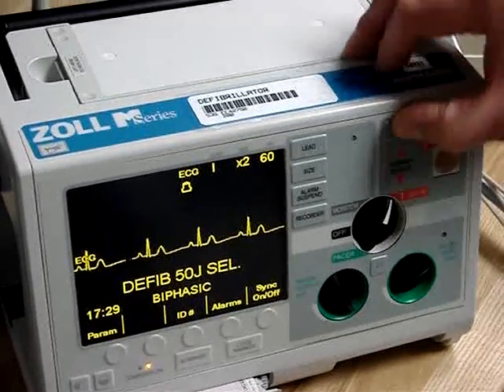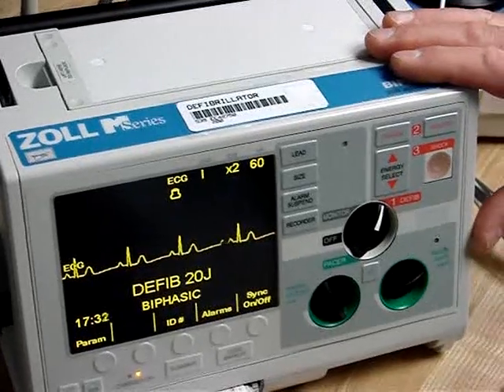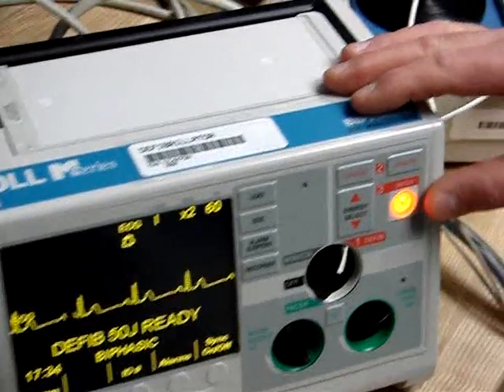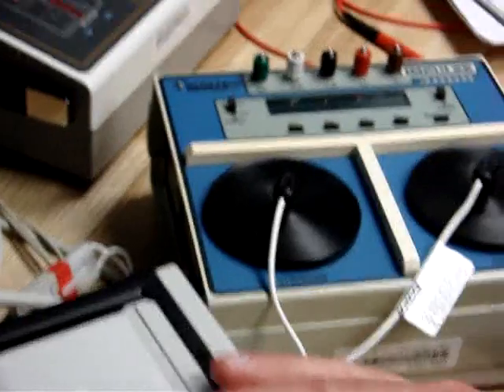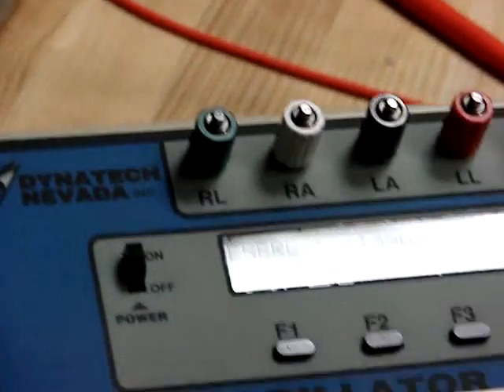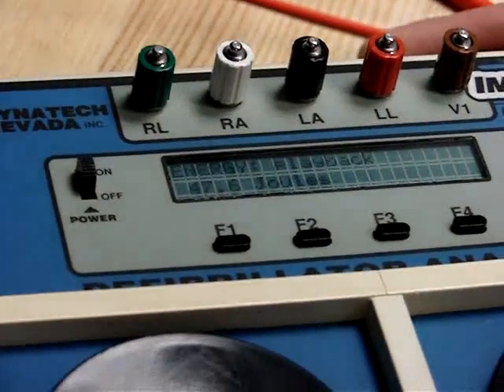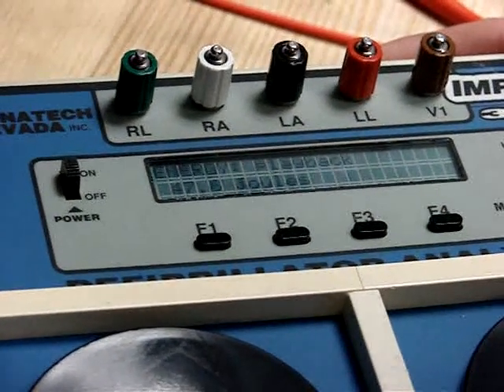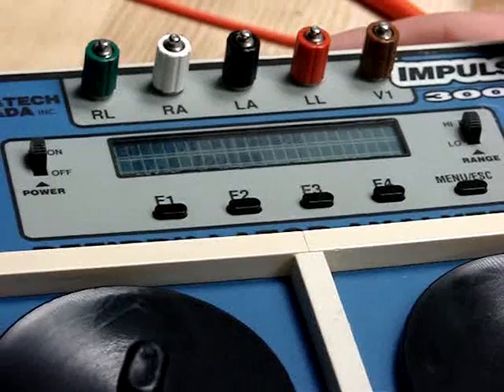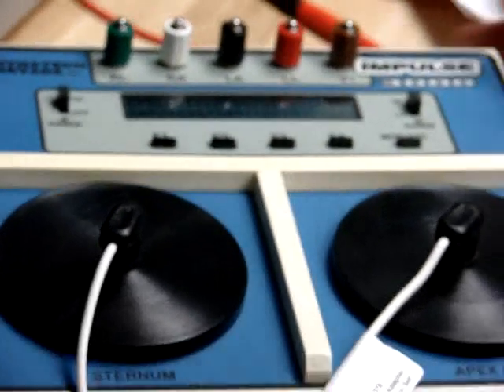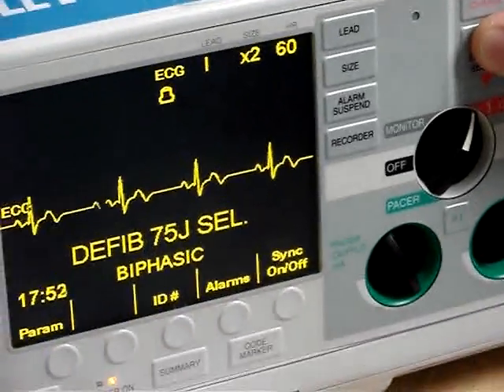We charge it. When it reaches 50, it gives us the shock light. We discharge, and then we're going to check to make sure we have a plus or minus 15% reading on our analyzer, and we are reading 47.6 joules, so that's well within the 15% plus or minus. So now we'll move our energy level up to 150.